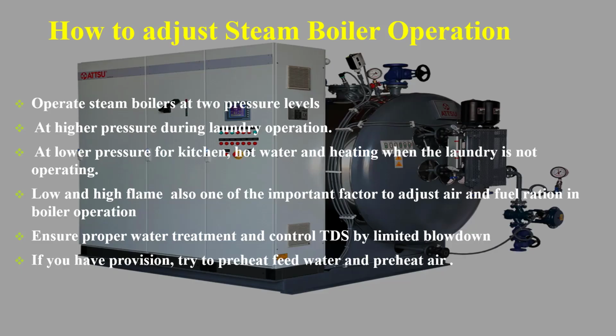How to adjust steam boiler operation. Operate steam boilers at two pressure levels. For example, in a hotel, high pressure steam is mainly used at the laundry, where a maximum of 6 to 8 kilograms per square centimeter is required, whereas remaining applications like generating hot water or kitchen may require only low pressure steam. So based on laundry working hours you can have high steam pressure and the remaining time low pressure, as a setting in the boiler.